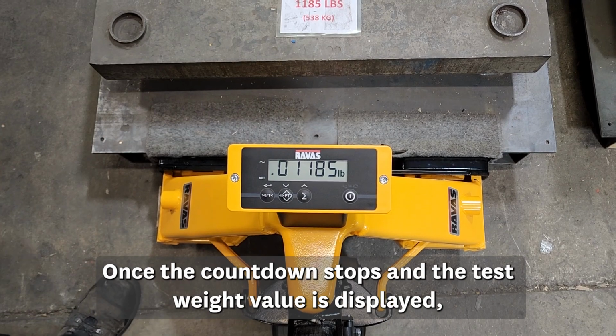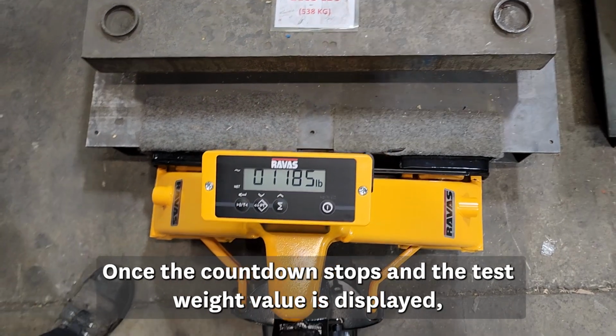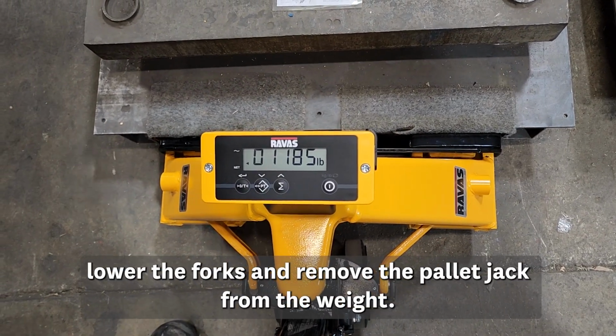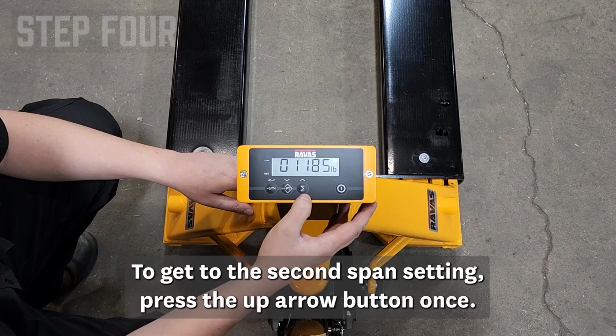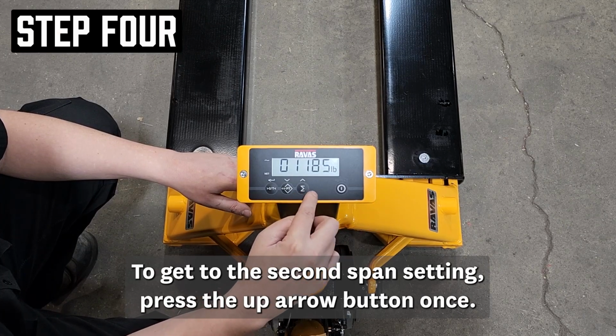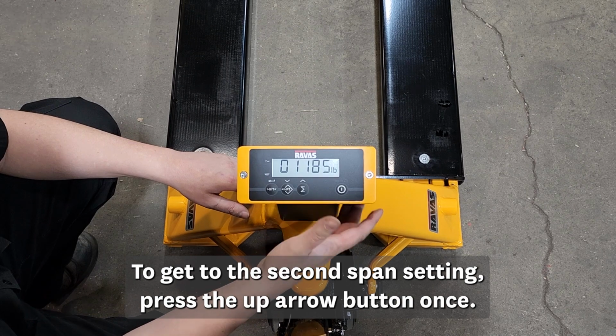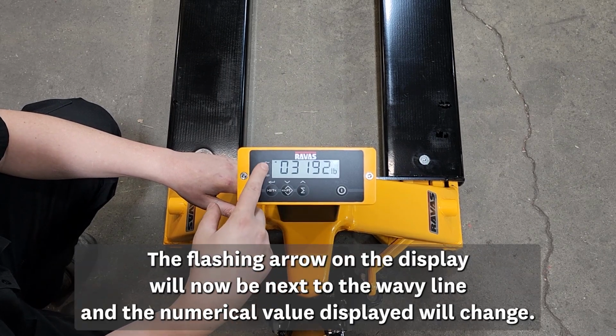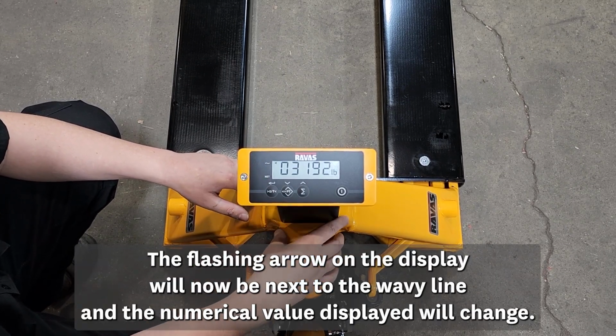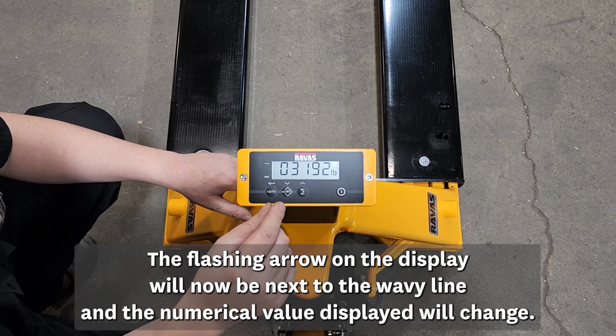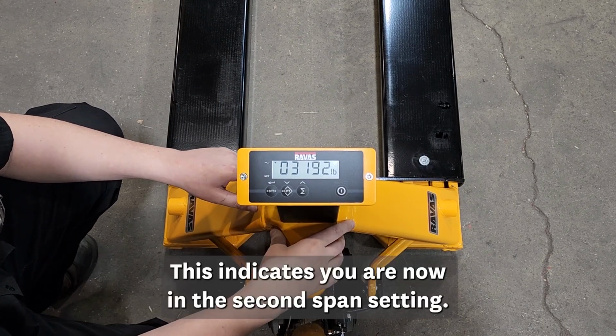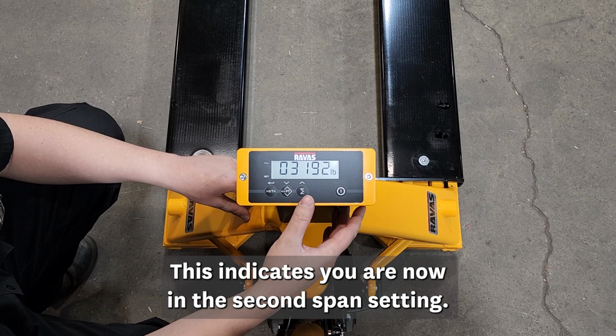Once the countdown stops, and the test weight value is displayed, lower the forks and remove the pallet jack from the weight. Step 4. To get to the second span setting, press the up arrow button once. The flashing arrow on the display will now be next to the wavy line and the numerical value displayed will change. This indicates you are now in the second span setting.